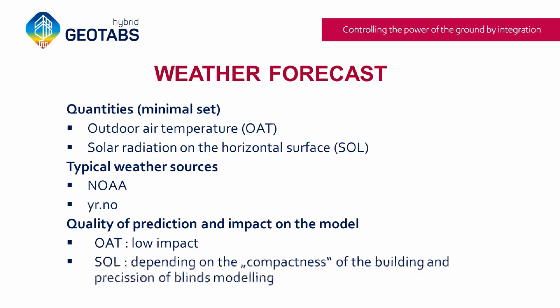From our experience, a mismatch in outdoor air temperature forecast has low impact on controller performance, but solar radiation is quite important. If the building is compact with small windows, or very good G-value glass or good blinds, then it doesn't have as much impact.